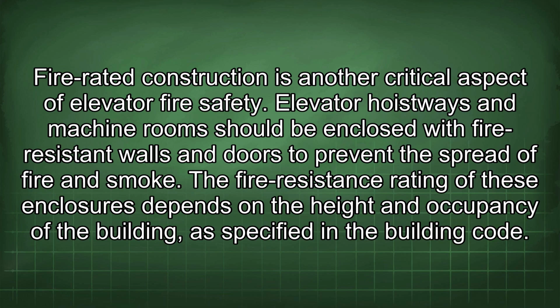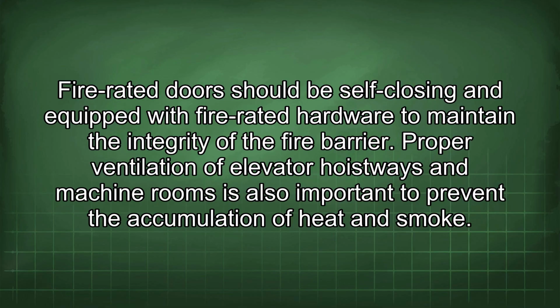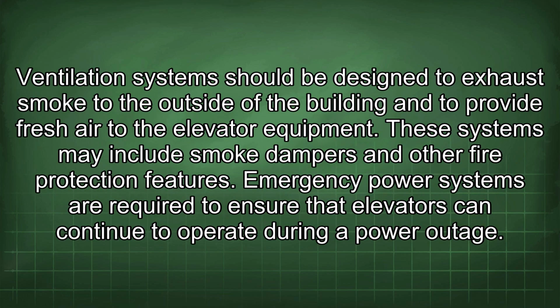Fire-rated construction is another critical aspect of elevator fire safety. Elevator hoistways and machine rooms should be enclosed with fire-resistant walls and doors to prevent the spread of fire and smoke. The fire resistance rating of these enclosures depends on the height and occupancy of the building, as specified in the building code. Fire-rated doors should be self-closing and equipped with fire-rated hardware to maintain the integrity of the fire barrier. Proper ventilation of elevator hoistways and machine rooms is also important to prevent the accumulation of heat and smoke. Ventilation systems should be designed to exhaust smoke to the outside of the building and to provide fresh air to the elevator equipment.